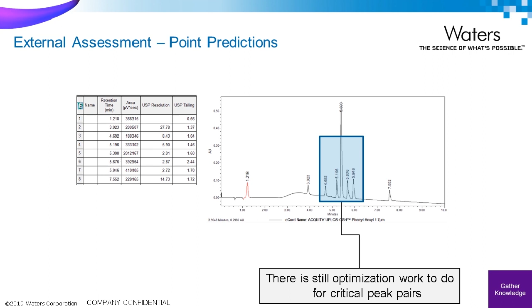So to begin method optimization, we take that graphic that we looked at earlier and the conditions that we set, and we expand that region to include the areas where we may show failure as well. We're moving now away from just the things that are most likely to affect selectivity, which are pH, gradient slope, and column type. And then we will now add in things like flow rate and temperature, which are typically secondary effectors of separation. This also allows us to calculate robustness for those parameters as well.